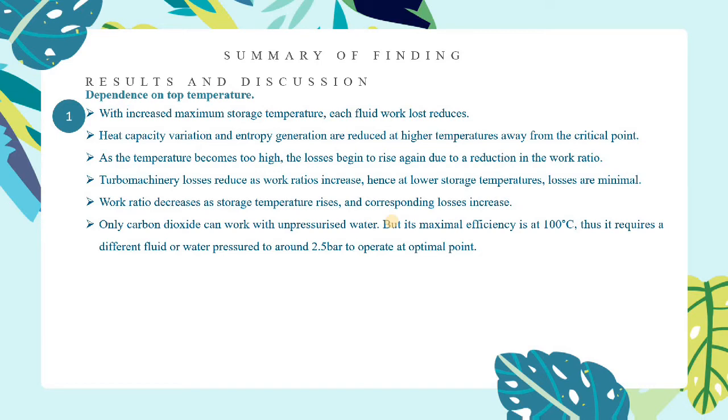But only carbon dioxide can work with unpressurized water, with its maximum efficiency at 100 degrees Celsius. Thus, it requires a different fluid or water pressure of around 2.5 bar to operate at the optimal point.